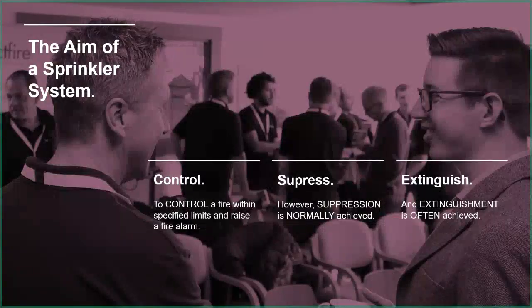That's really what we're looking for from a sprinkler system: to control a fire within specified limits and raise a fire alarm. The area we're looking to control depends on the building. Is it a large open plan warehouse, or an office or residential home where everything's compartmented and we want to keep the fire in the room of origin? In a large open plan environment, it'll be a certain square meterage area we're looking to contain the fire within.